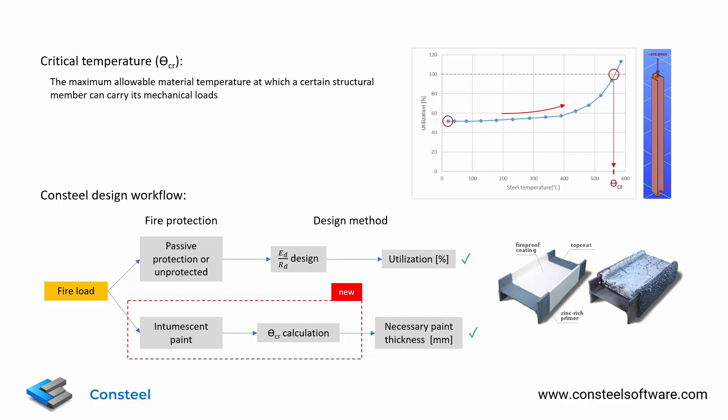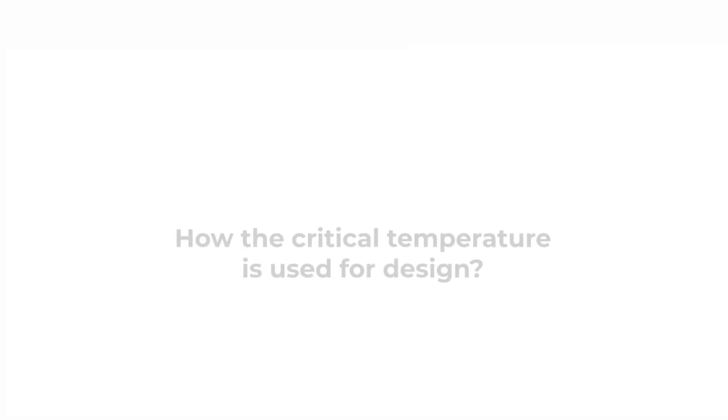That's where the critical temperature comes into play because in order to calculate it, we don't need to know the heat insulation capability of the fire protection. With the help of the critical temperature, we can determine the necessary paint thickness which would be our final goal for this kind of fire protection.